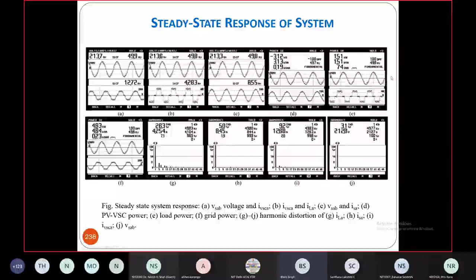You can think of a typical grid current THD of 5%, when the voltage THD was also 3.1% and the load THD was 26.3%. So it is providing the load compensation. You can see the grid current is at typically unity power factor here, and the minus means power is fed to the grid, and the load is consuming 1.51 kilowatt out of that.